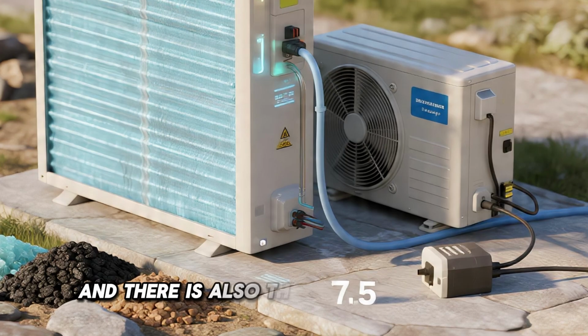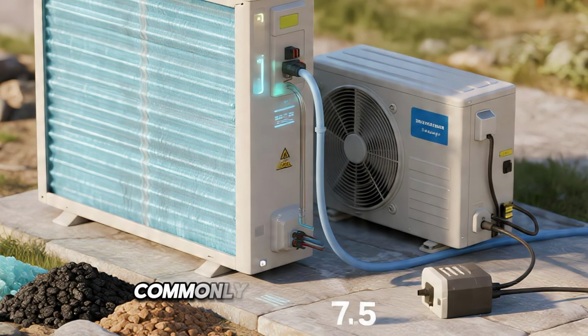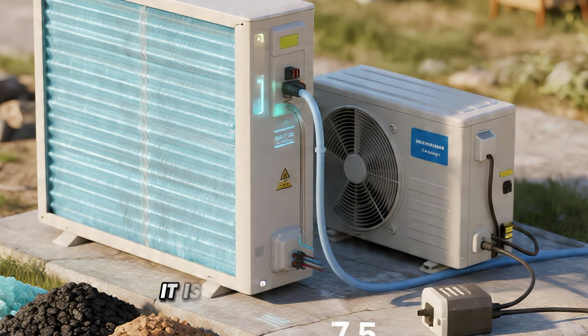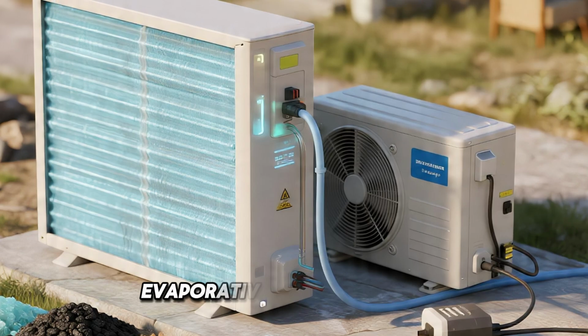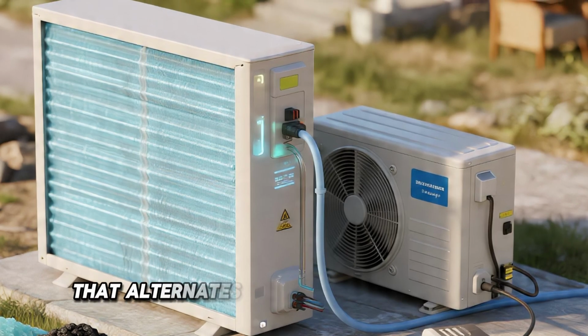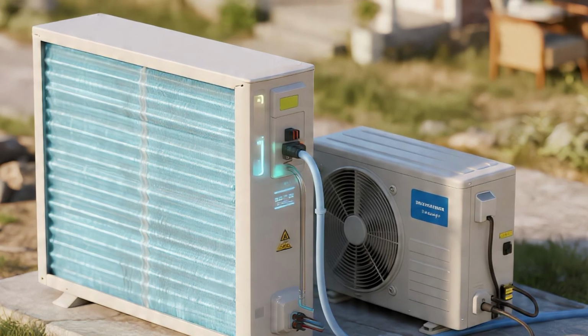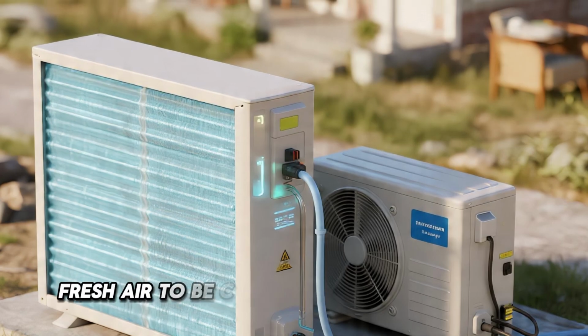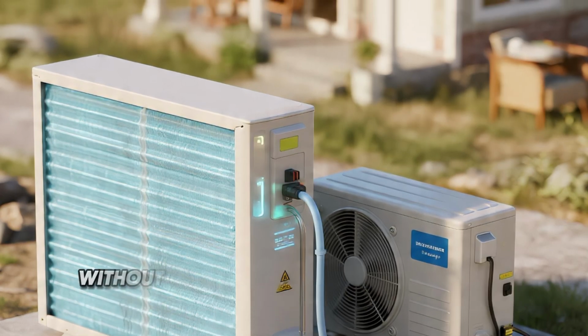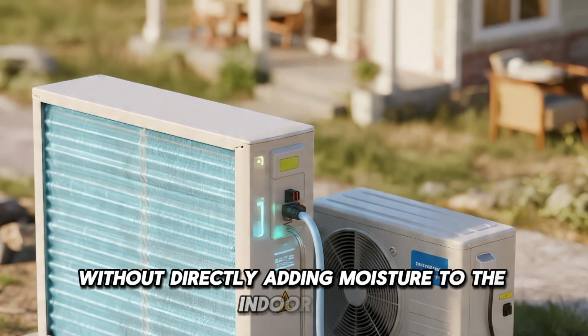And there is also the Maisotsenko cycle, commonly called the M cycle. It is an ingenious, indirect evaporative cooling method that alternates wet and dry air passages, allowing incoming fresh air to be cooled toward its dew point without directly adding moisture to the indoor air.